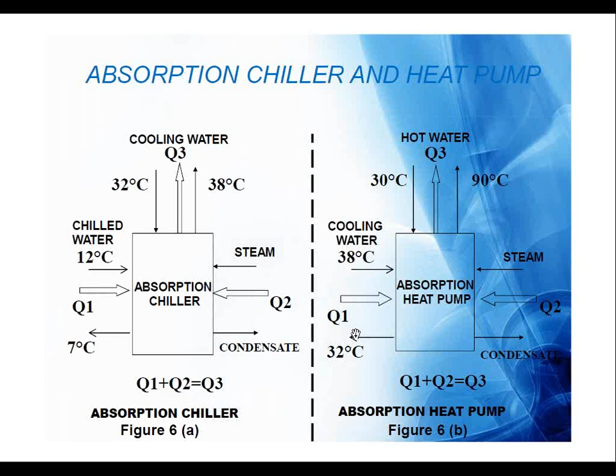Going by a simple payback calculation, if we consider around 10 cubic meters of water which is supposed to be heated from 30 degrees to 90 degrees, consider this as an application of feed water heating for the boiler. This 10 cubic meters of water is not coming from the condensate recovery, so it is makeup water or DM water coming from your DM plant, and has to be heated from 30 degrees to 90 or 105 degrees. As for the heat pump, we can limit it up to 90-95 degrees. Above that, it will not be possible to generate heat from the heat pump.